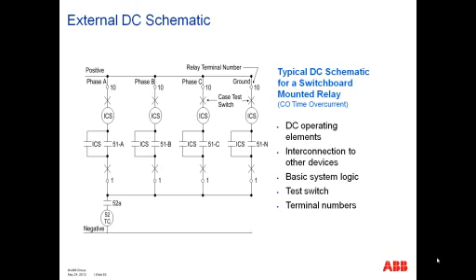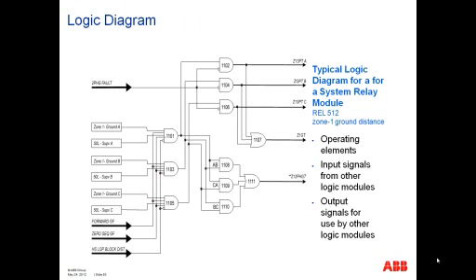Next. Then you would have the external DC schematic, which is, if you will, the logic diagram of an electromechanical relay. You have your indicating contactor switches and your device operating contacts, and it shows what needs to operate to trip the appropriate circuit breaker trip coil, the 52TC. And of course, more modern relays are provided with logic diagrams to show you various elements and how those elements are combined together to operate certain logic quantities.